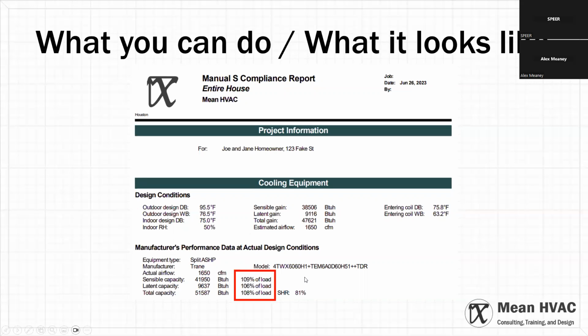I don't like to be under by that much, but that is the current limit. For total capacity, both sensible and total have the same rules. We want it between 90% and 115% for single stage equipment, 120% for two stage equipment, and 130% for variable capacity equipment like inverter technology.